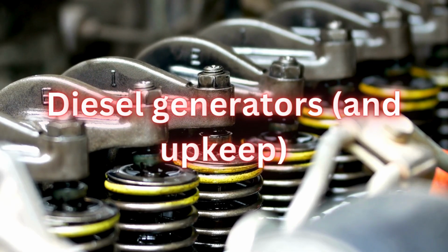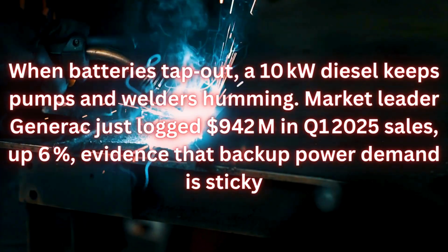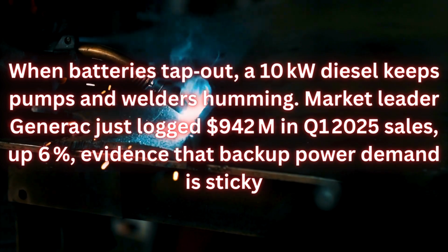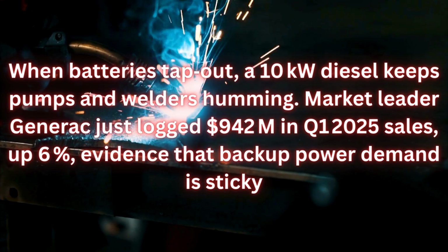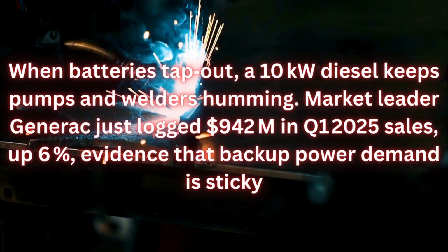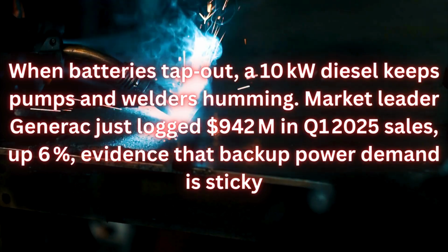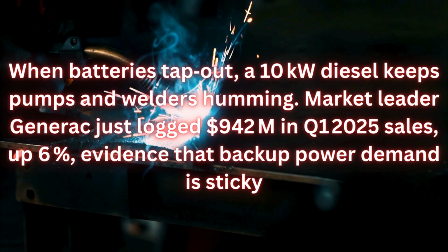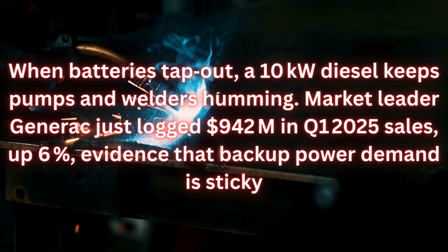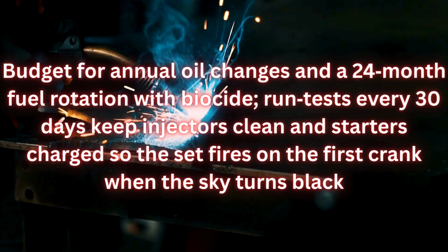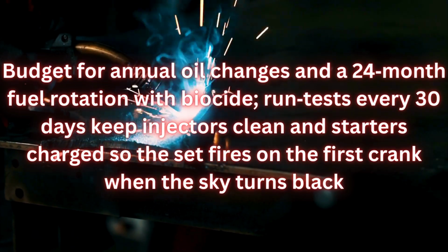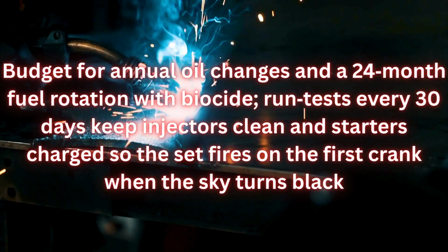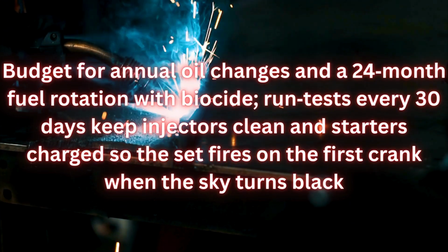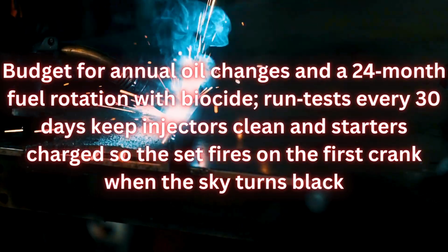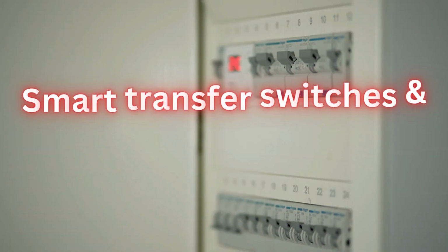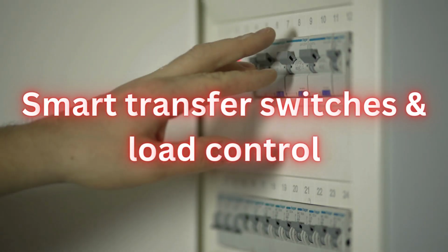Diesel generators and upkeep: when batteries tap out, a 10 kilowatt diesel keeps pumps and welders humming. Market leader Generac just logged $942 million in Q1 2025 sales, up 6%, evidence that backup power demand is sticky. Budget for annual oil changes and a 24-month fuel rotation with biocide. Run tests every 30 days, keep injectors clean and starters charged so the set fires on the first crank when the sky turns black.